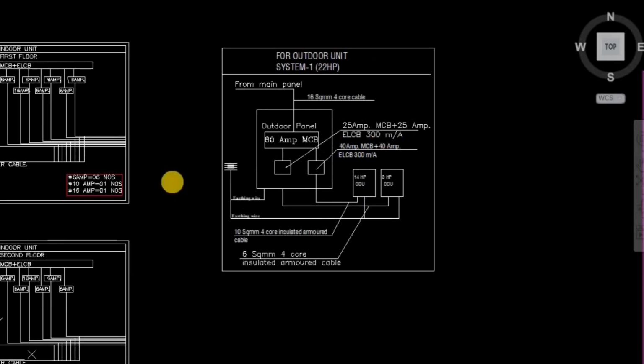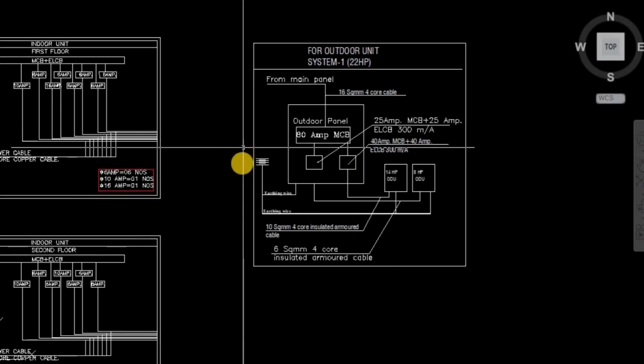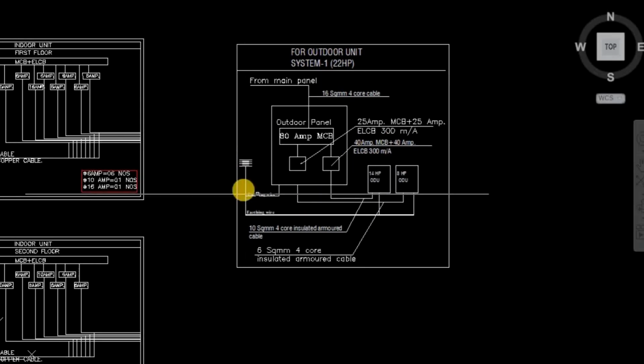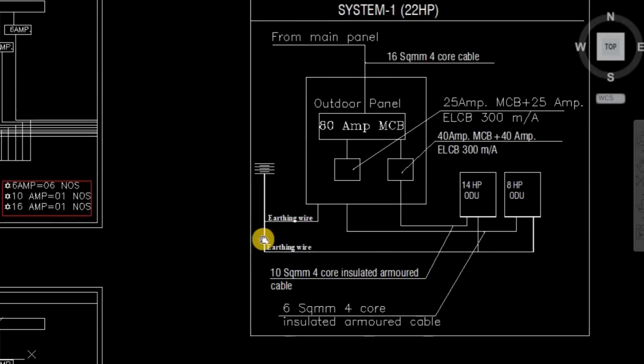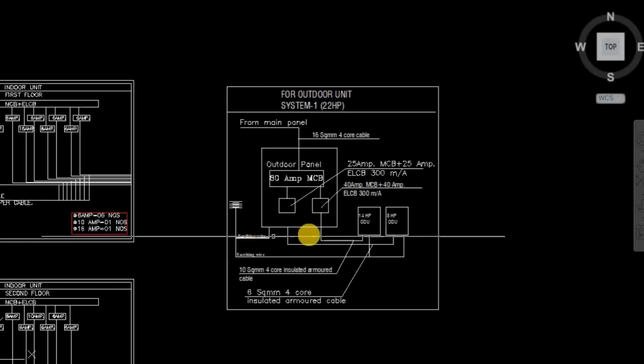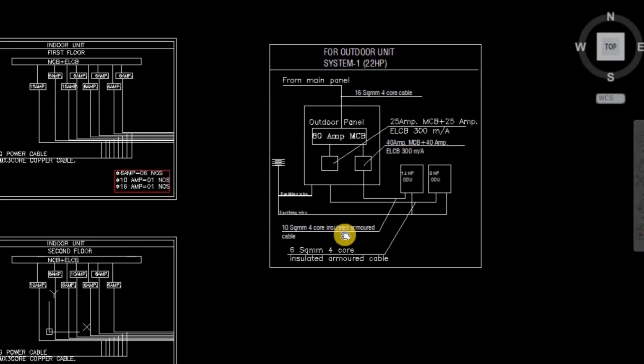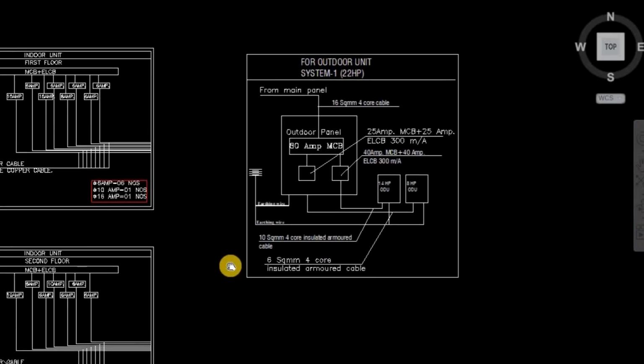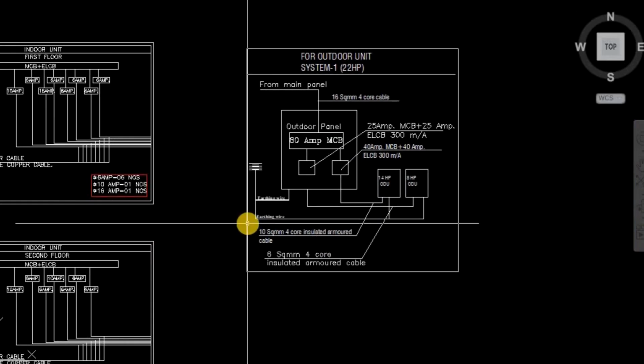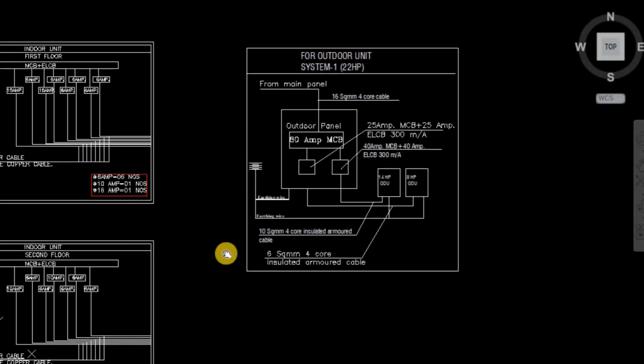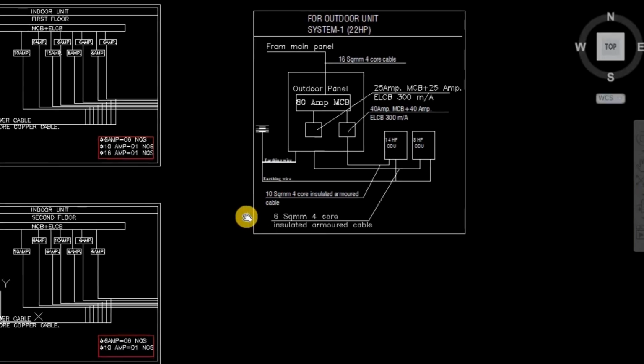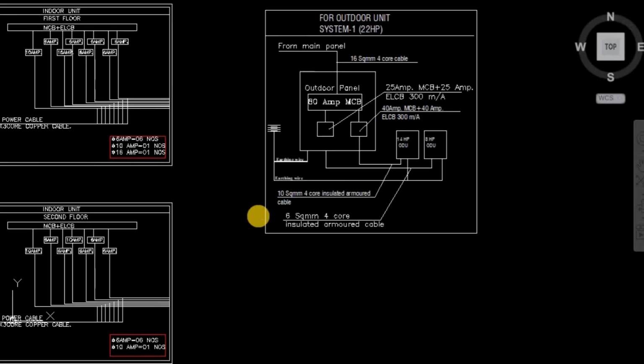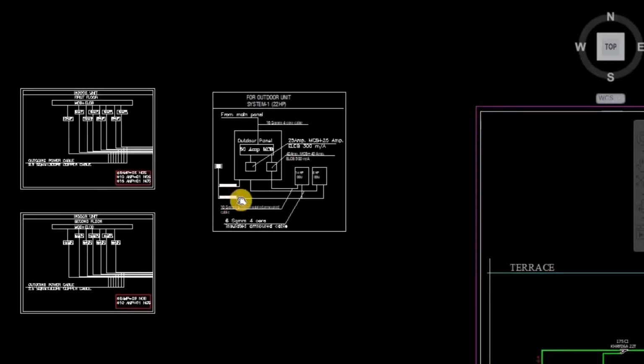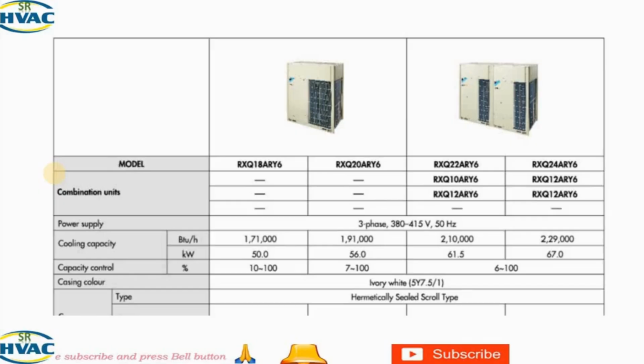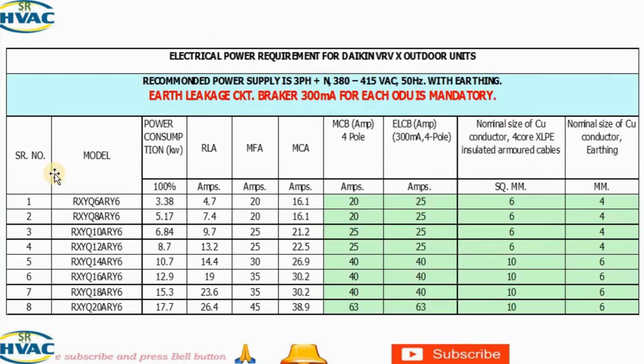Okay friends, and some installation tips to ensure a smooth installation. Double check the wiring diagram before final connection. Use proper cable glands and conduit for neat wiring. Okay, perform an insulation resistance test to check the cable health. Always follow lock out, tag out safety procedure while working on a live circuit. Finally, cross verify the wiring with the Daikin installation manual. Okay friends, these are the basic tips for installation. That completes the overview of Daikin electrical details from power supply to the control wire.